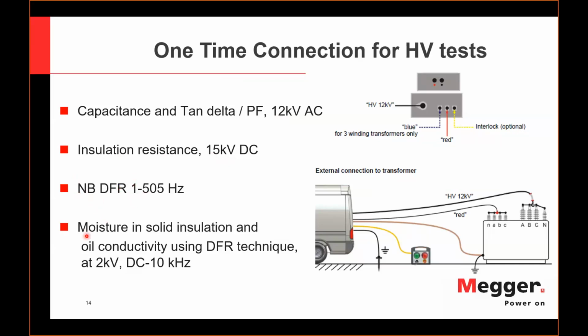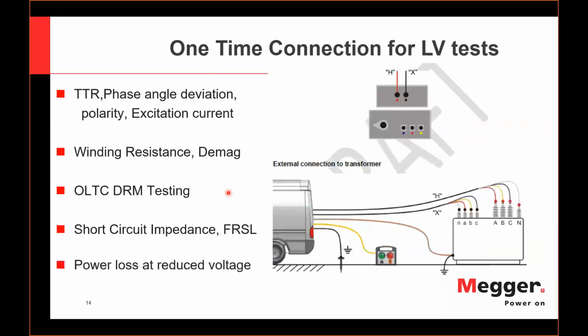And you can bring the ultimate DFR full band or broadband technique, even with the amplifier up to 2 kilovolt, and conduct the full spectrum assessment from DC up to 10 kilohertz frequency to get the material properties and to establish moisture content in your cellulose and conductivity of oil. This is done with one connection, and then the switch box enables the interconnection of these instruments automatically per mouse click inside the van.